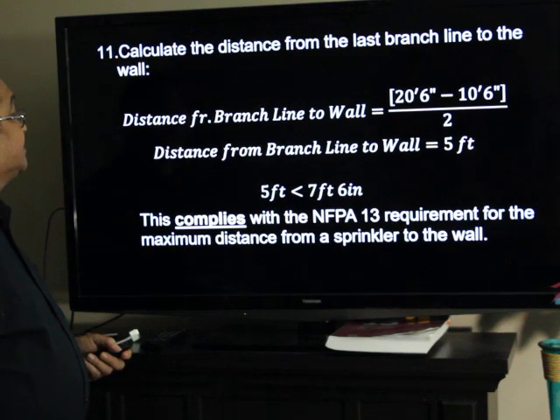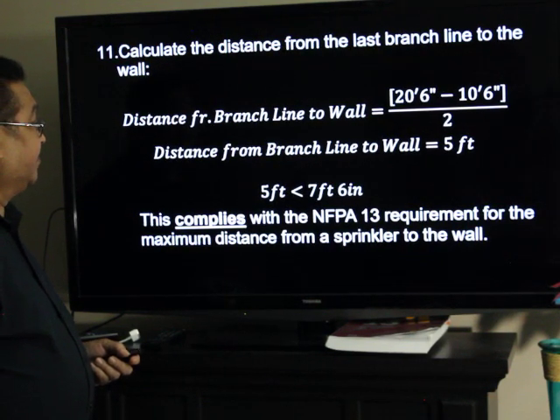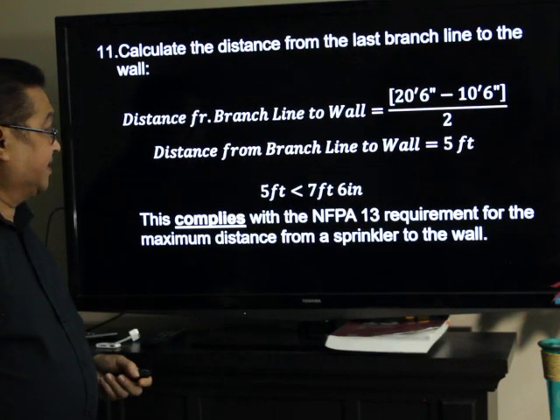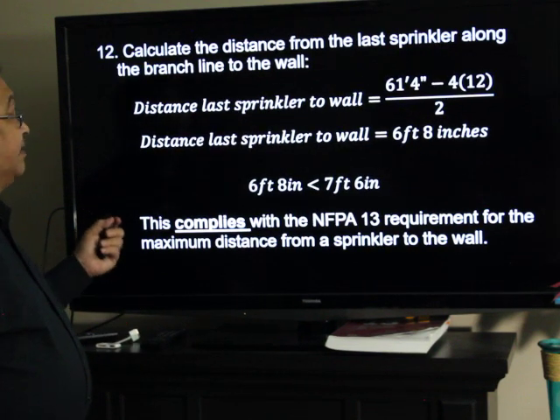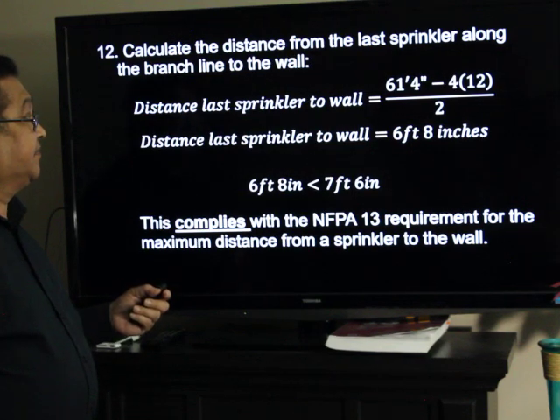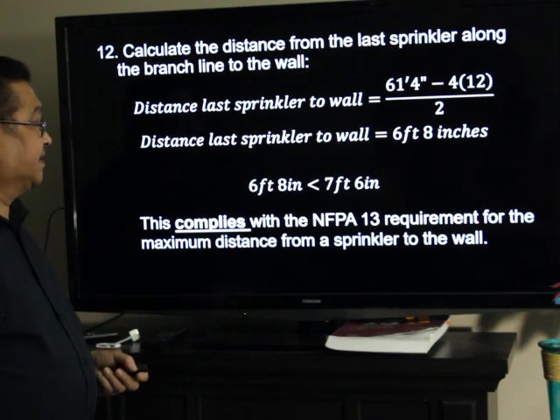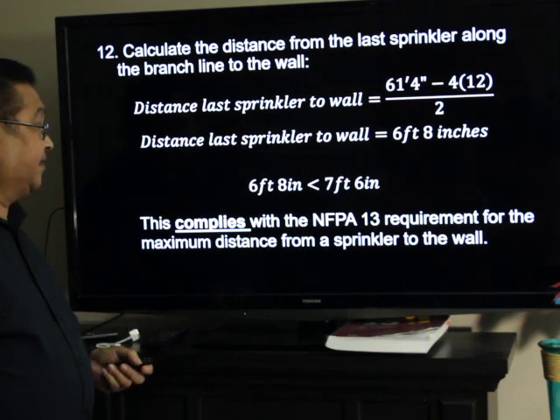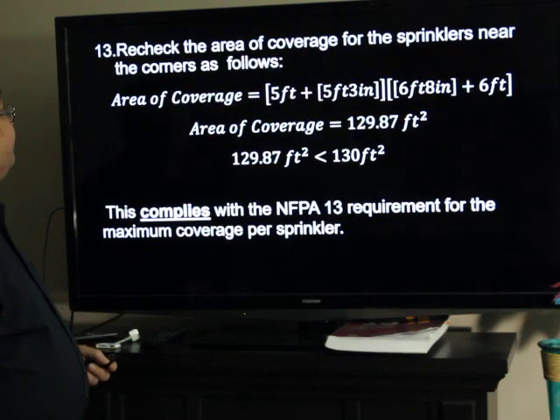Calculate the distance from the last branch line to the wall: 20.5 minus 10.5 feet, all over 2, will be 5 feet. It's less than 7 feet and 6 inches, so that is okay — it complies with the NFPA requirement. And calculate the distance from the last sprinkler along the branch line to the wall: 61 feet 4 inches, minus 4 times 12, all over 2. We have 6 feet and 8 inches, which is less than 7 feet and 6 inches, which also complies with the NFPA 13 requirement for the maximum distance from the sprinkler to the wall.